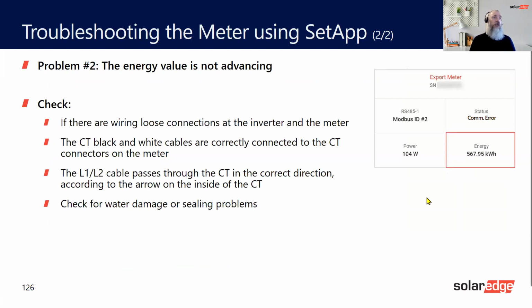Again, make sure that the correct CT is on the corresponding phase. So don't twist them together. Don't run them with AC cables. Try and make sure that they're separate. If they are too long, then please cut them to the longest one as such, or the shortest one. Make sure they're all the same length. Don't twist them together. Try and keep them separate. And please don't have coils of cable in your enclosure as well.